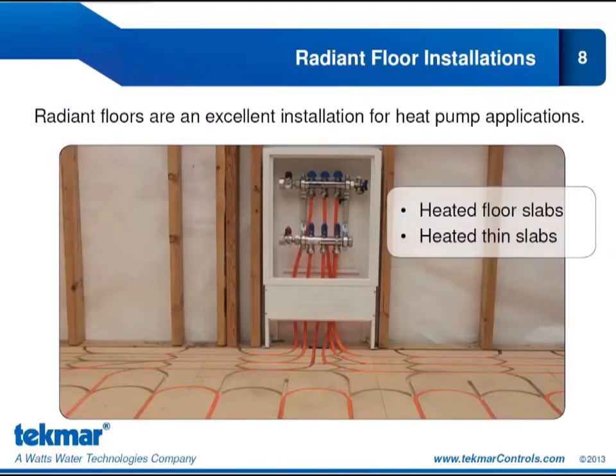Now, as we mentioned earlier, radiant floors are an excellent installation for heat pump applications because they operate best, in fact, with low water temperatures. So we are able to keep that entering load water temperature very low and to maintain a high level of occupant comfort. So they are an excellent application for the geothermal design. Now, the types of radiant floors that are suited for geothermal applications are the heated floor slabs and the heated thin slabs. Both of these will be optimized at low water temperatures.